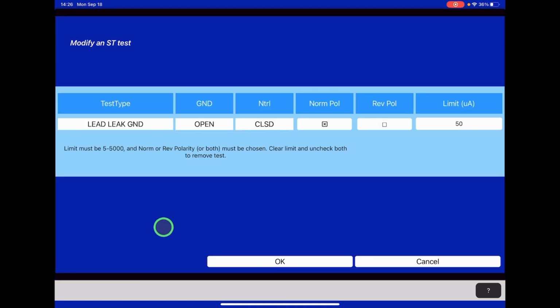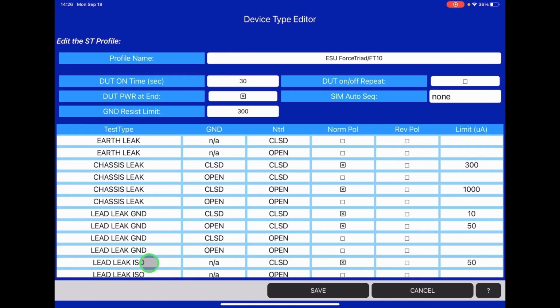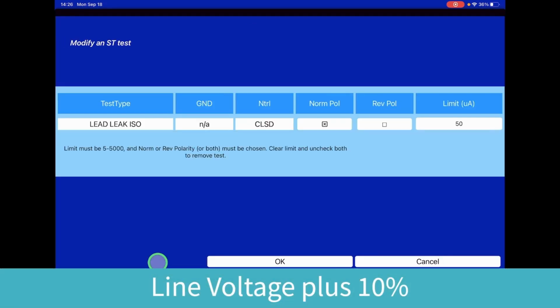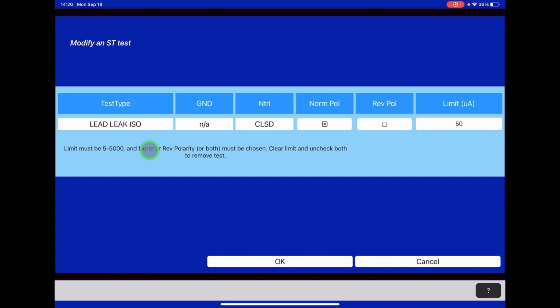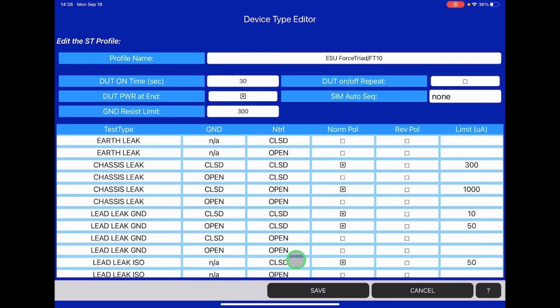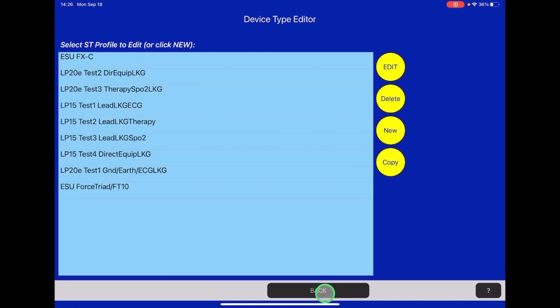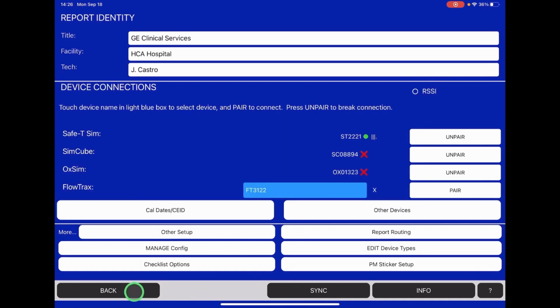Also need to do it with a fault condition, which will be the ground open. So we're going to repeat the same test with the ground open the second time. In normal polarity, the limit is 50 microamps. And then the very last test is a lead leakage ISO test, or a lot of times it's referred to as a MAP test, a mains on applied parts test. This is where we're taking 120 volts AC and applying it to the leads. In the case of this test, we need to do it with the neutral closed in normal polarity, and the limit is 50 microamps as well.